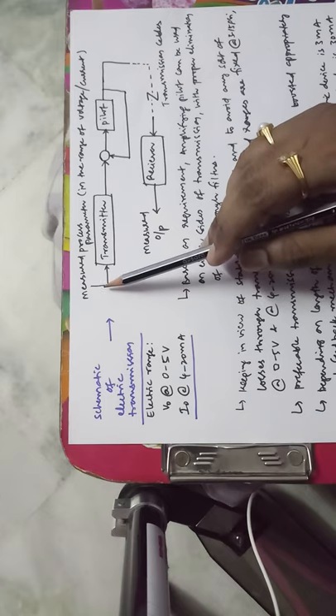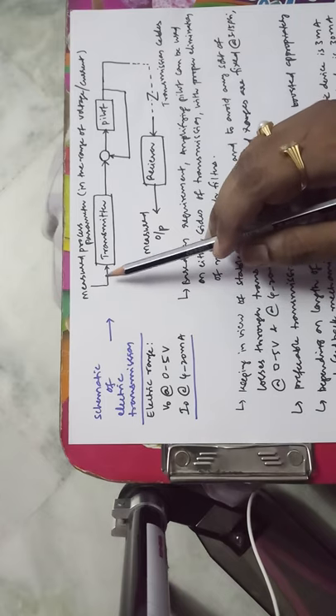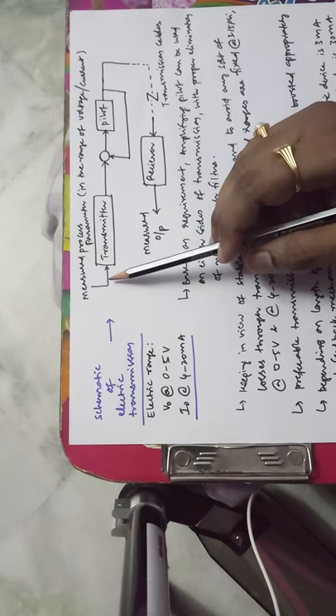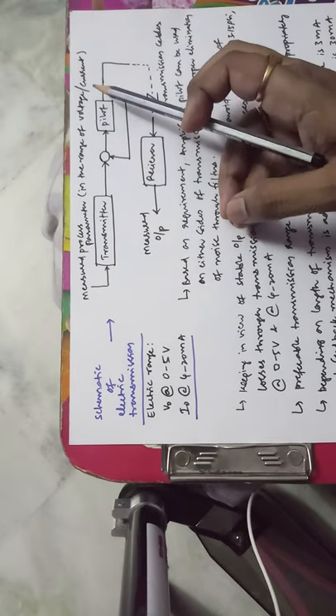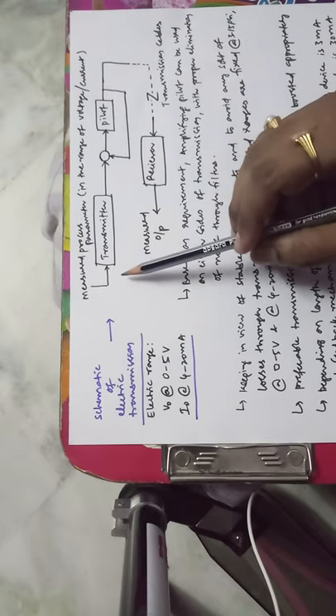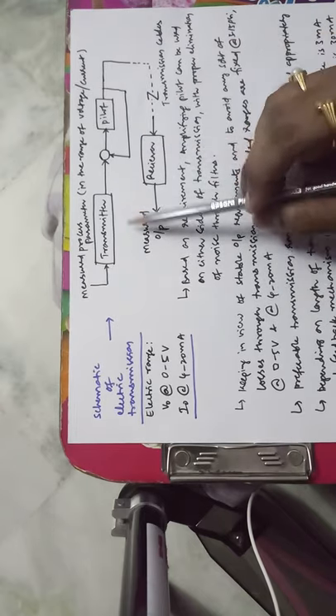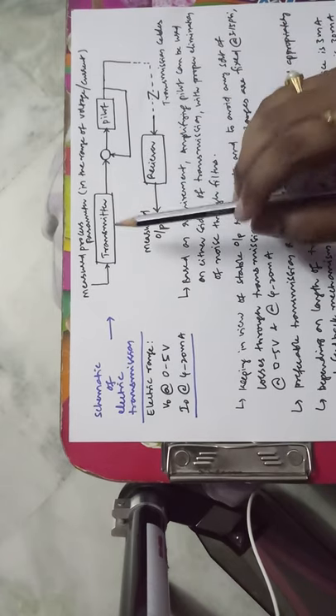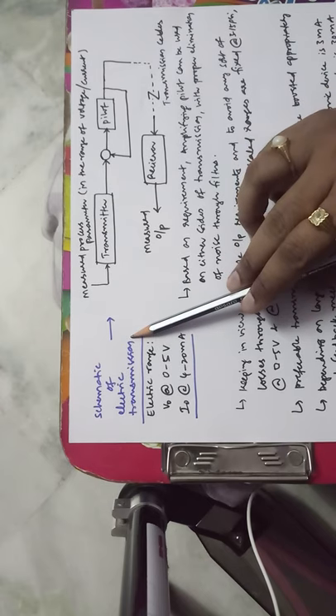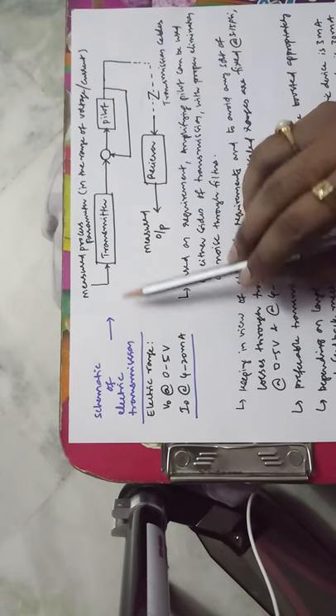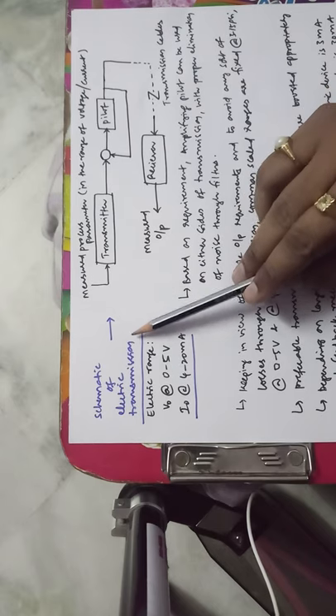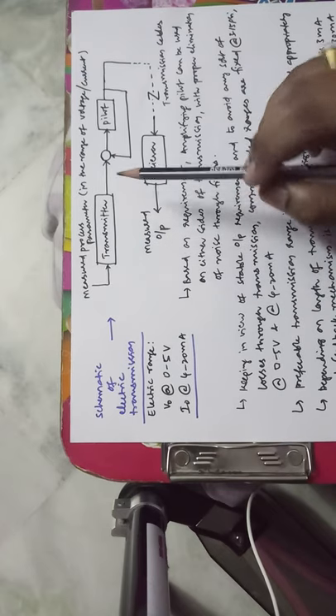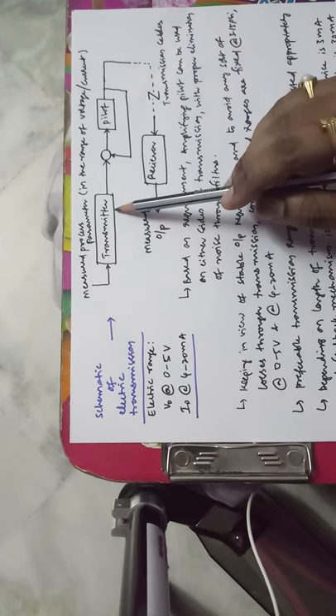In pneumatic transducers, the measured process variable is converted to a pressure parameter. In electrical transmission, the measured process parameter is converted to an electrical variable — either voltage or current. If it is voltage, it is called a voltage telemetry system; if it is current, it is called a current telemetry system. Electrical transmission systems are preferred to avoid problems associated with pneumatic transmission.